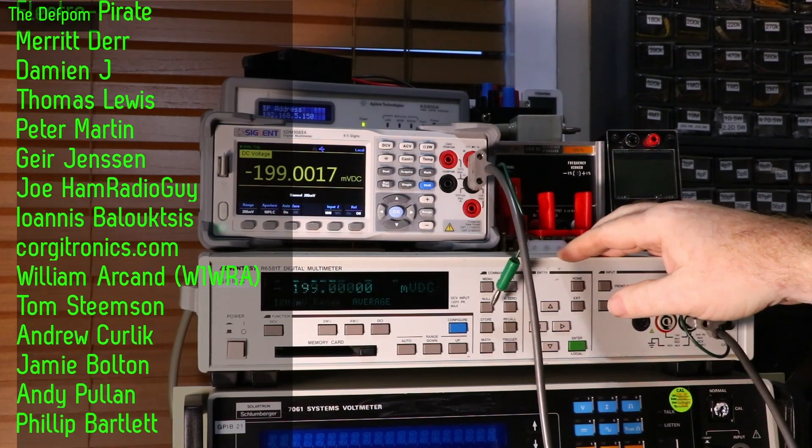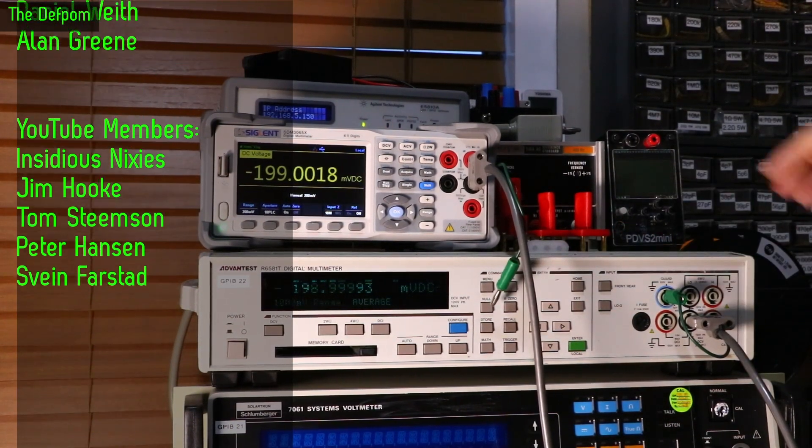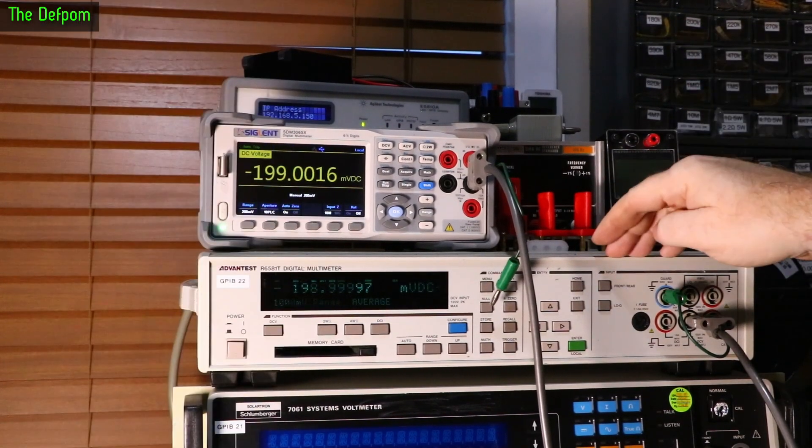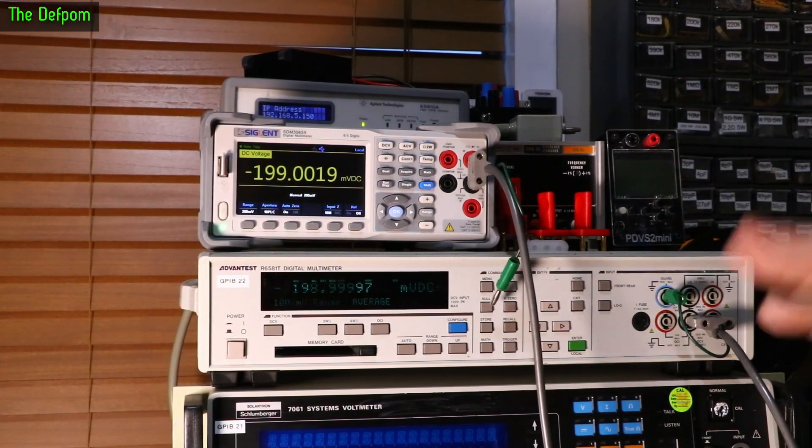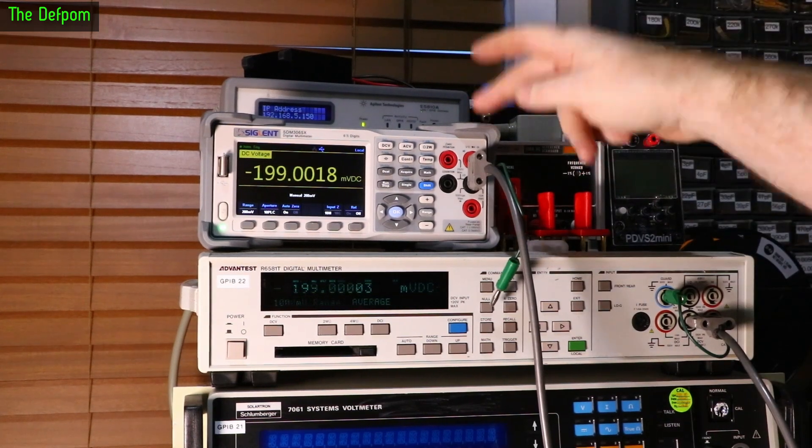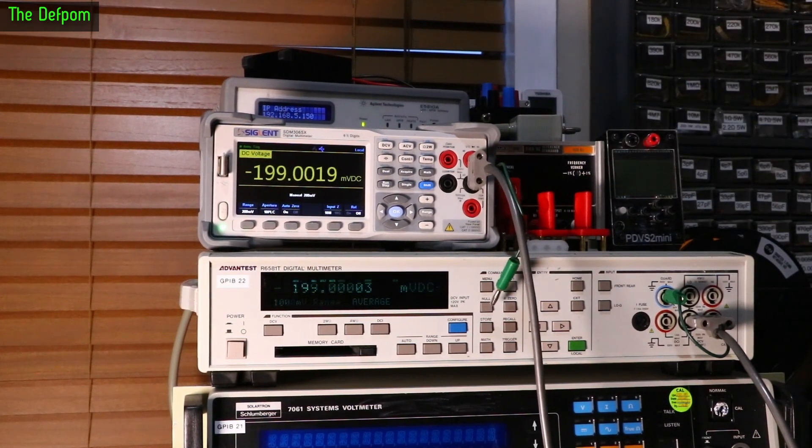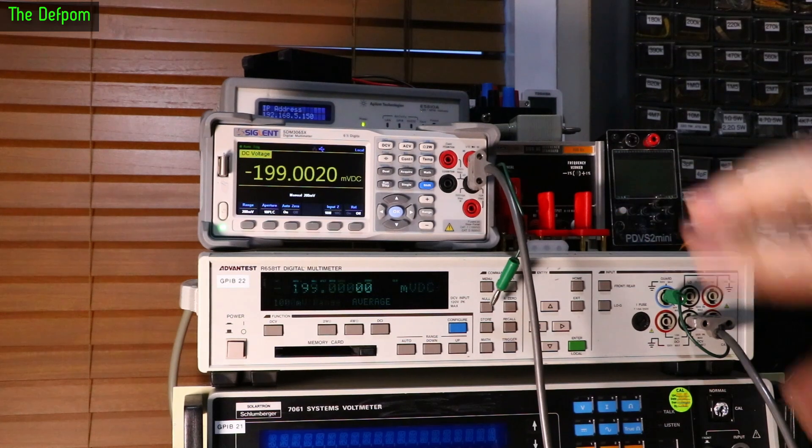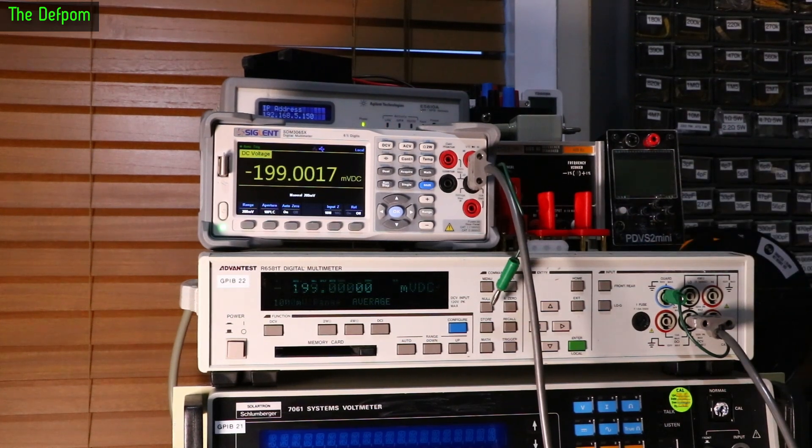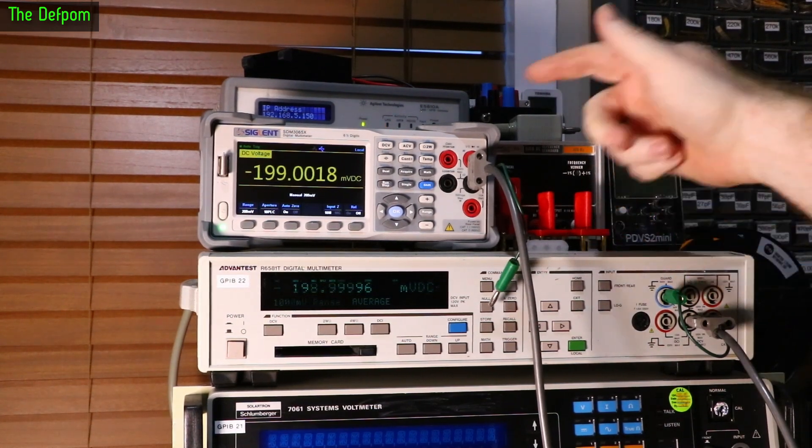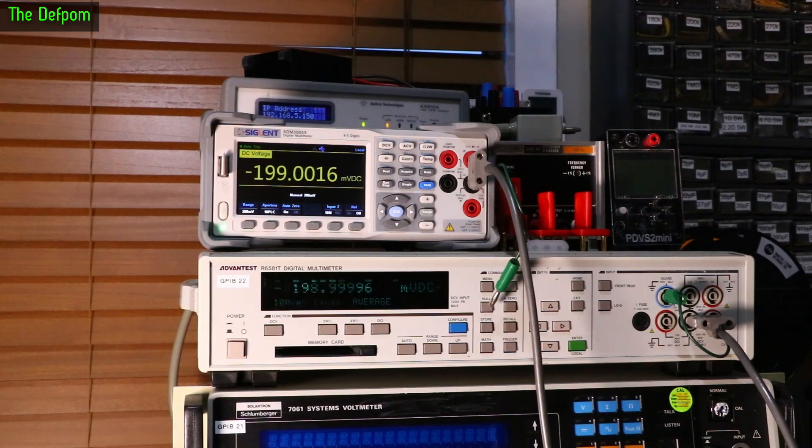I've got my Advantest R6581T 8.5-digit multimeter here. These aren't perfect multimeters - they do have linearity issues, but for calibrating a 6.5-digit should be no problem. It's still two orders of magnitude more than this meter. As long as you've got one more digit, it's fine.